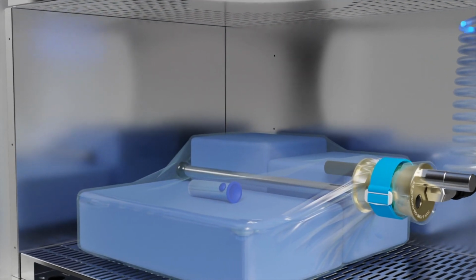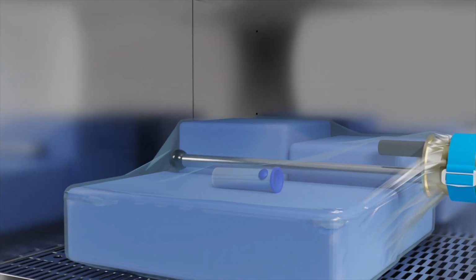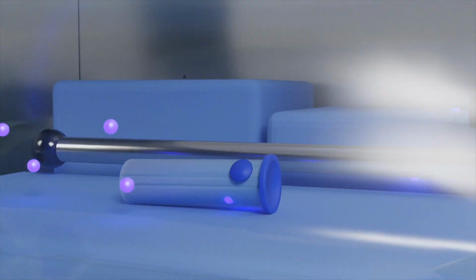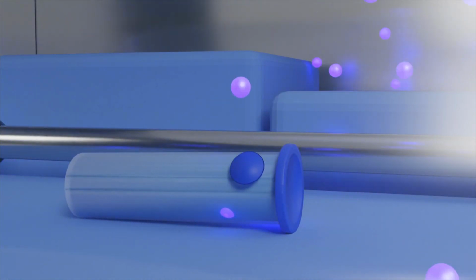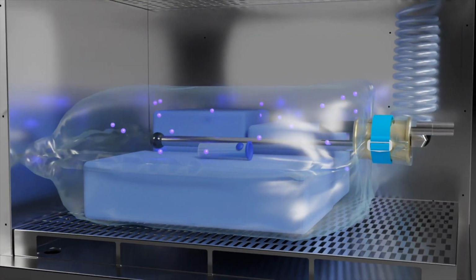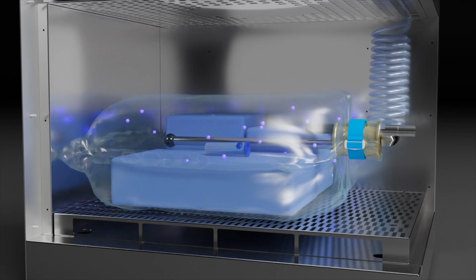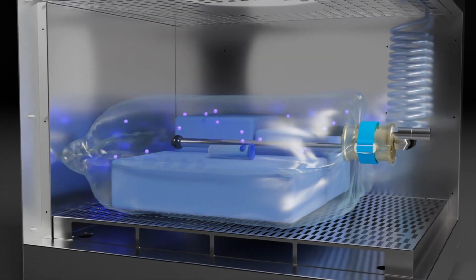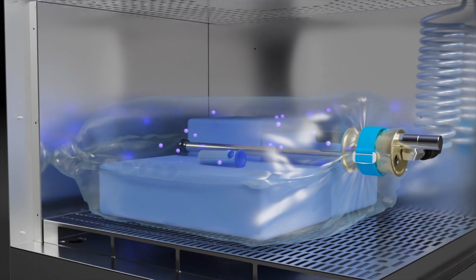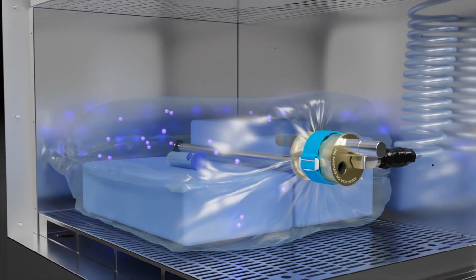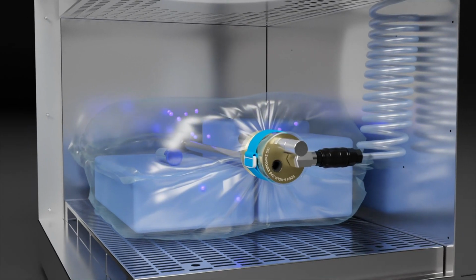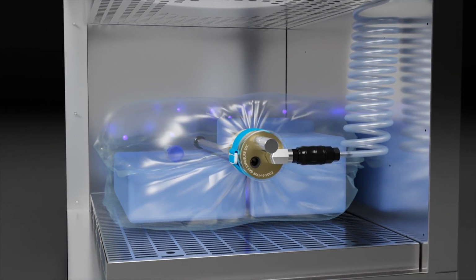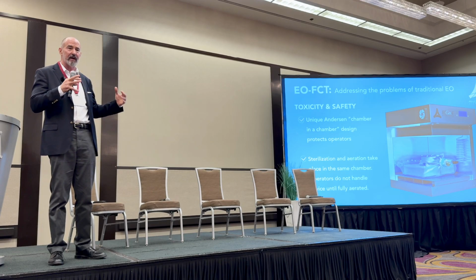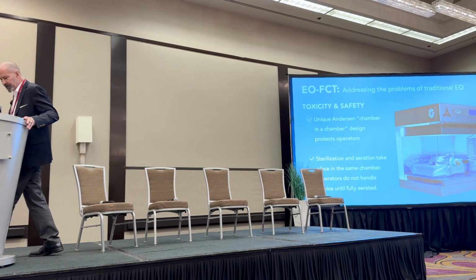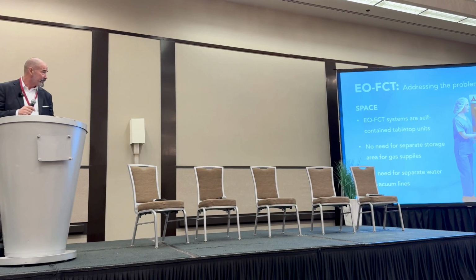There is no dead space, and so when you activate the gas cartridge, you get a very high gas concentration with a very small amount of gas. The sterilization bag is operated inside of a cabinet that is under constant negative pressure. It acts like a dedicated vent hood. So throughout the cycle, if there are any leaks, if there are any problems, the sterilization cabinet draws that off. This is a belt and suspenders approach. We call it a chamber inside a chamber, but this provides a high degree of confidence that you're not going to end up with gas in the workplace. Again, very different from any other system that came before.